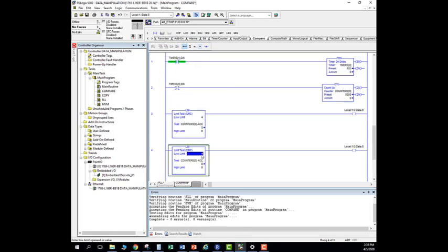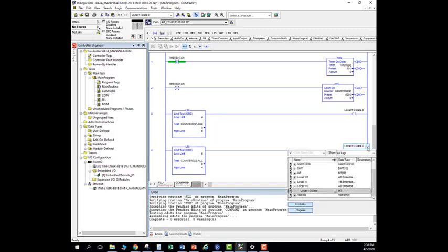And here I want to flip-flop the ranges. So I want this to be a 6, and I want this to be a 4. Because what we're going to do is look for the numbers that are outside the range between 6 and 4. Remember we talked about that in lecture. This is looking for inside the range of 4 to 6. This is looking outside the range between 4 and 6. So any number outside of 4 and 6 will turn this output on. So we're going to turn on output 1.